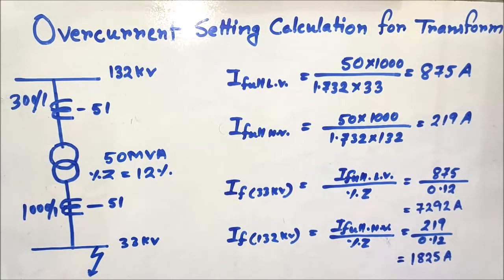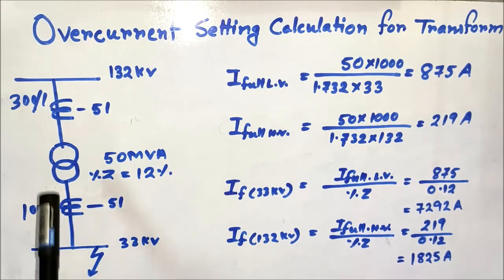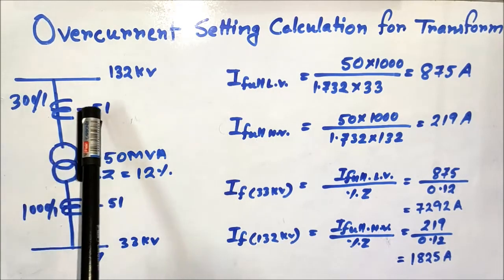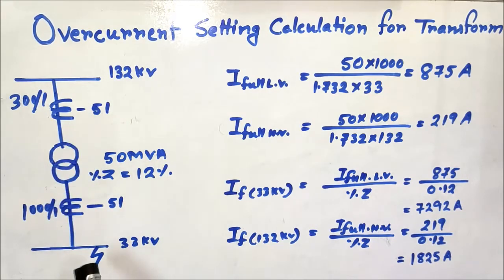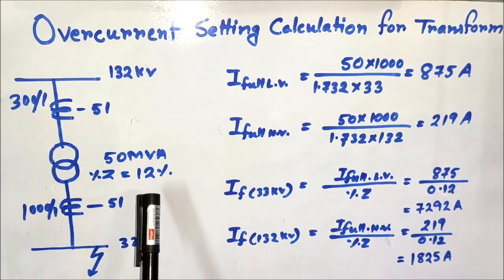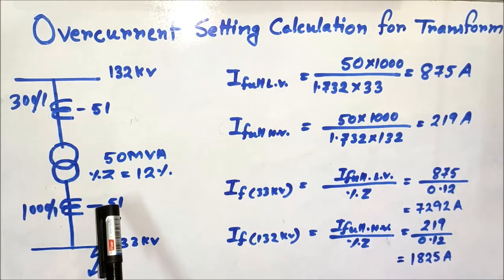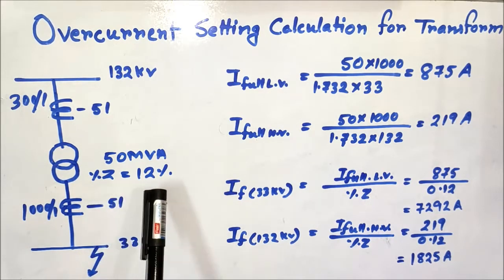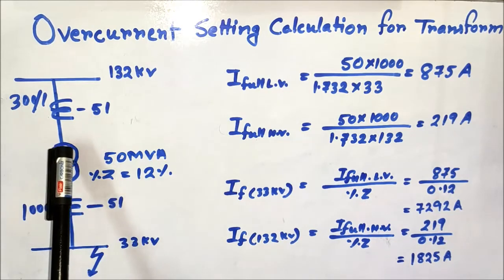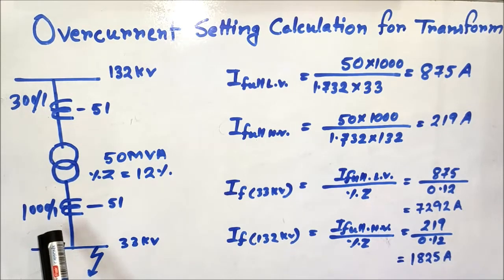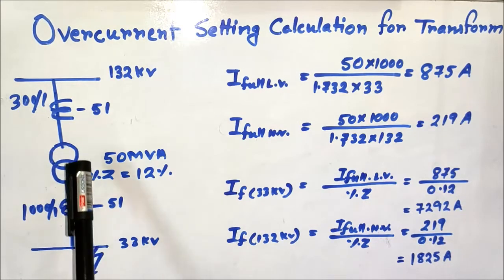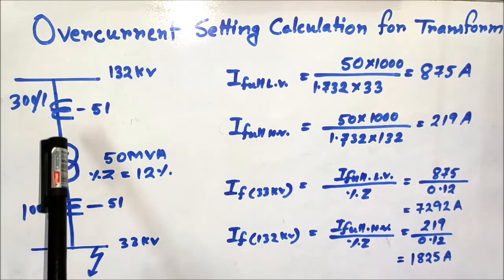Hello friends, welcome back to my channel. Today I will discuss overcurrent setting calculation for a transformer. In this figure, you can see a 132kV bus with a transformer connected between 132kV and 33kV. The transformer rating is 50 MVA, 132/33kV, with a percentage impedance of 12%. The HV CT ratio is 300/1 and the LV CT ratio is 1000/1. We will calculate the settings for both LV and HV overcurrent relays.